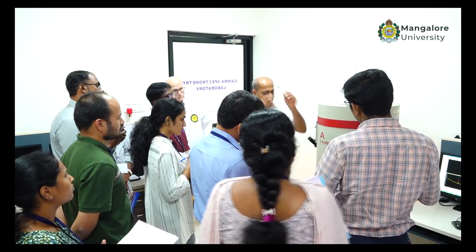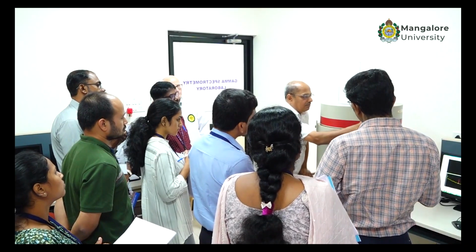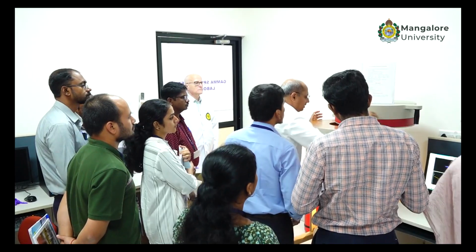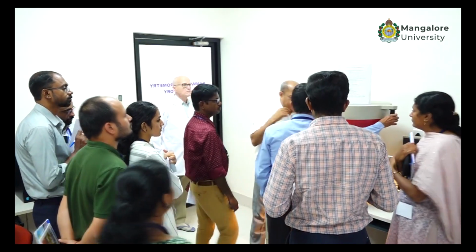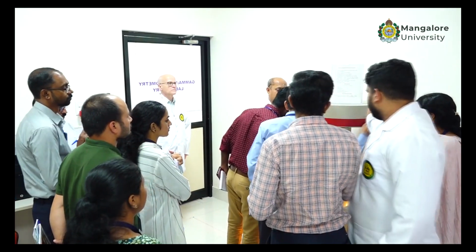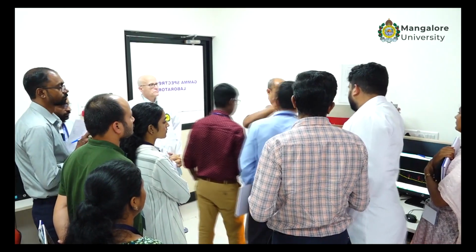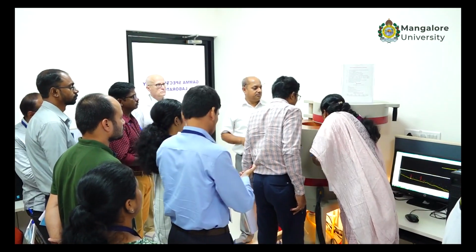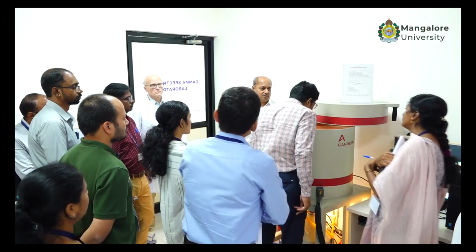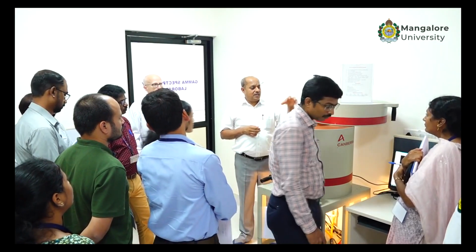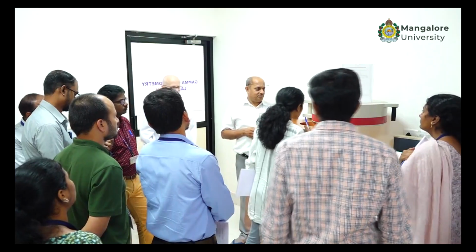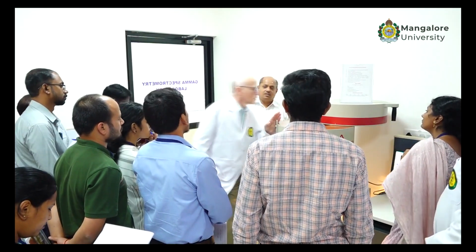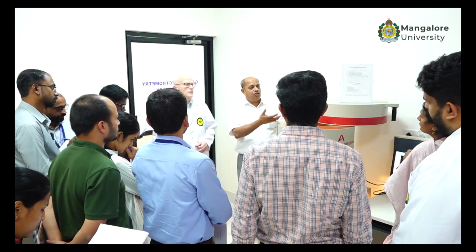You see, there is a gap between the detector and shielding. The detector is there and there is a cavity. This is the gap. So there we always flush nitrogen, because it reduces the background. Normally, this air gap will have radon as well, and radon progeny will accumulate.